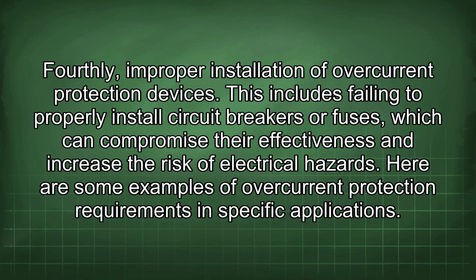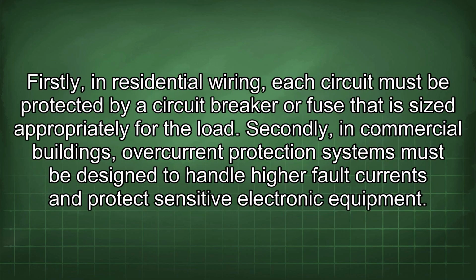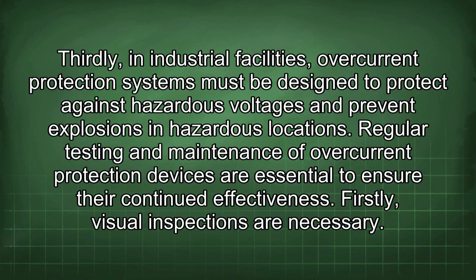Fourthly, improper installation of overcurrent protection devices. This includes failing to properly install circuit breakers or fuses, which can compromise their effectiveness and increase the risk of electrical hazards. Here are some examples of overcurrent protection requirements in specific applications. Firstly, in residential wiring, each circuit must be protected by a circuit breaker or fuse that is sized appropriately for the load. Secondly, in commercial buildings, overcurrent protection systems must be designed to handle higher fault currents and protect sensitive electronic equipment. Thirdly, in industrial facilities, overcurrent protection systems must be designed to protect against hazardous voltages and prevent explosions in hazardous locations. Regular testing and maintenance of overcurrent protection devices are essential to ensure their continued effectiveness.